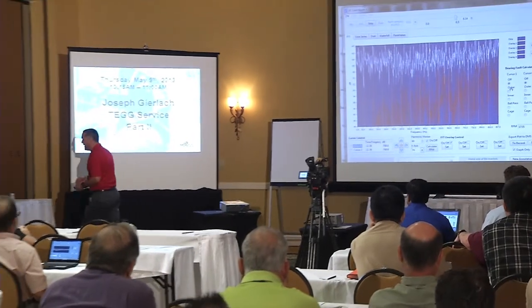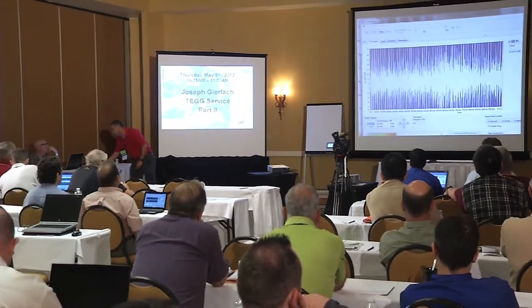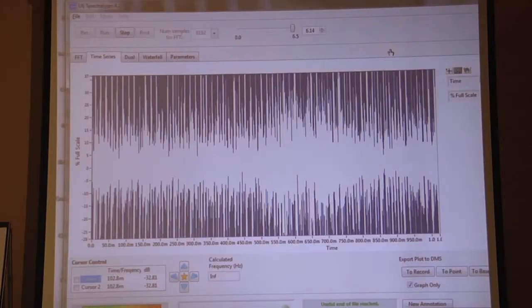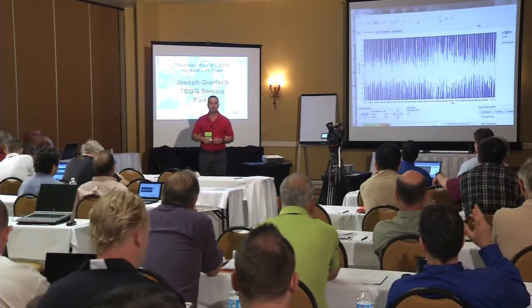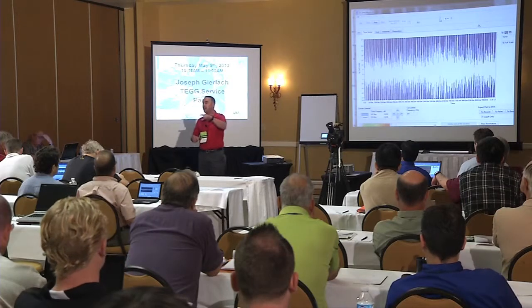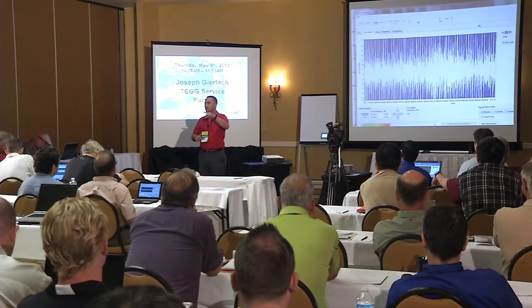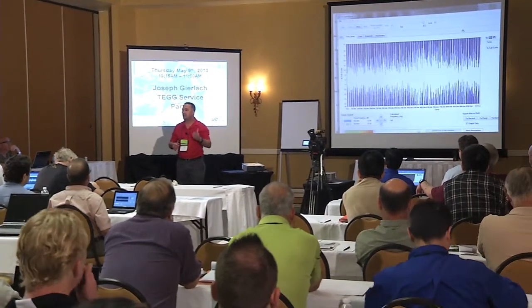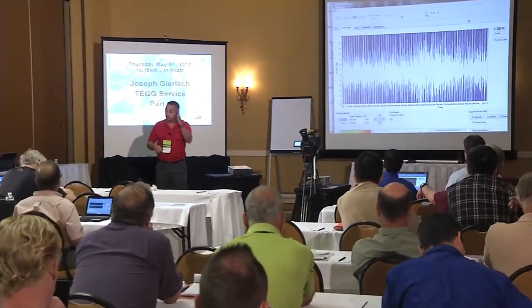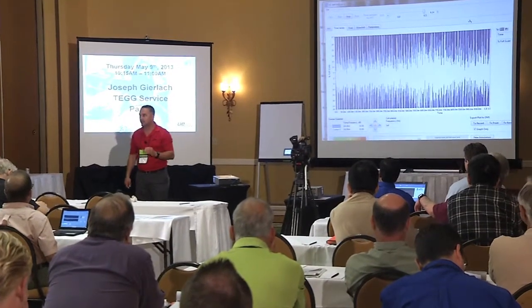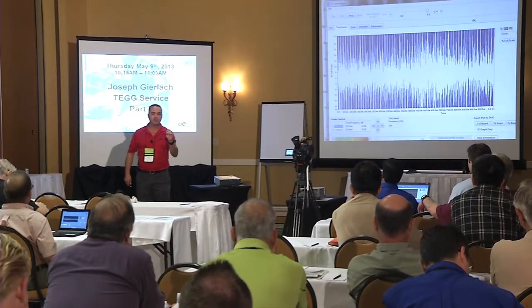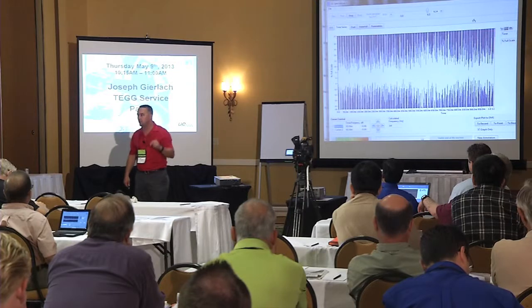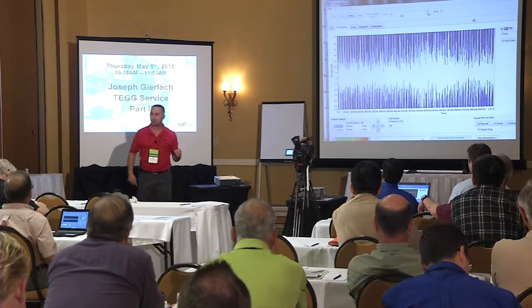So when I go to the time analyzer, what did we say about tracking we're looking for in here? What were the two things that we're looking for in the time analyzer? Yeah, the peaks that change and the changes in time. How frequently is it happening, right? And the more severe it becomes, the more frequently it occurs and more compacted in the view. But the whole thing is, the timing is not going to be uniform when the discharges are taking place.